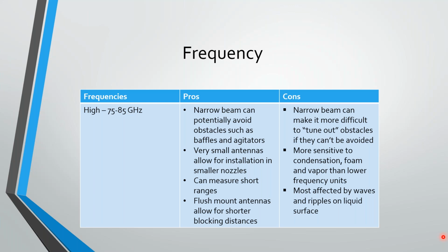Again, shorter blocking distances. This is something I didn't mention before, but when we were talking about guided wave radar earlier, there is kind of a dead zone, not only at the top, but also at the bottom on a guided wave radar. It could be 3 inches, 4 inches, depending. But there'll be an area where, if the liquid or the medium gets within that range, the instrument will not properly measure, known as a dead zone or blocking distance. In non-contact radar, we don't have one at the bottom, but we still have a dead zone at the top.